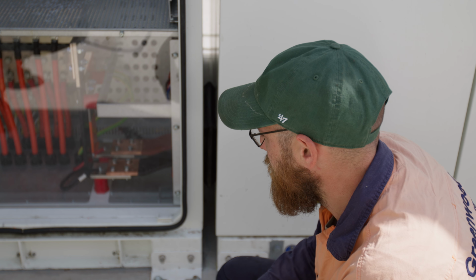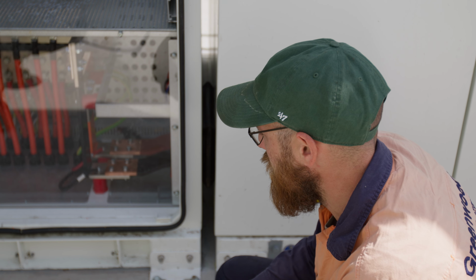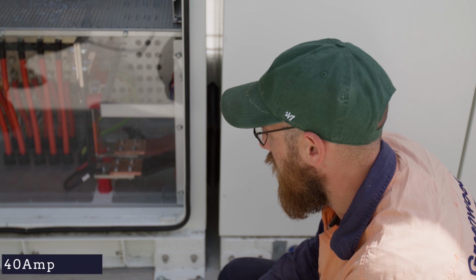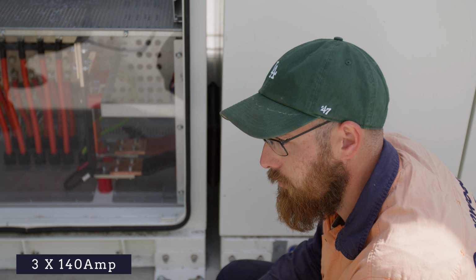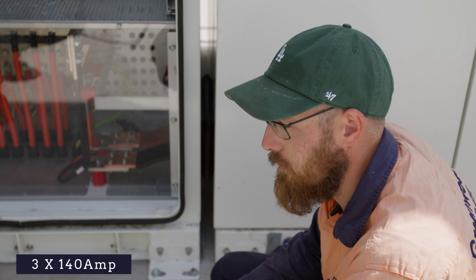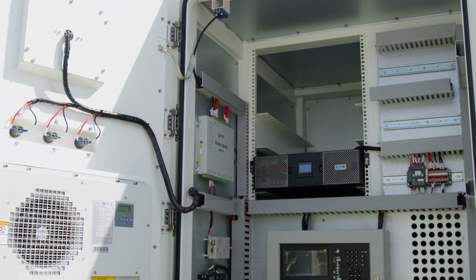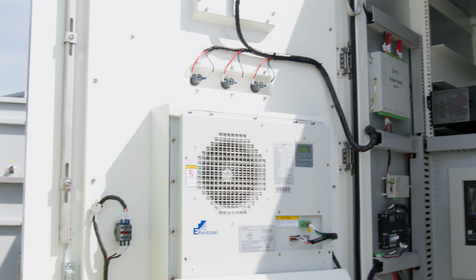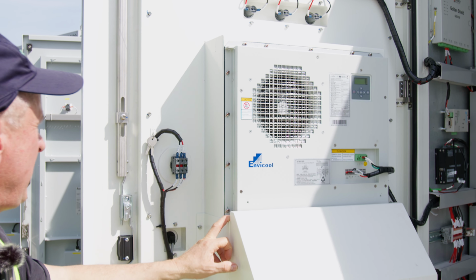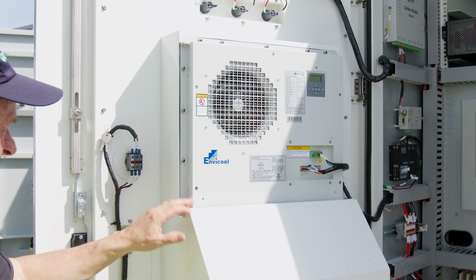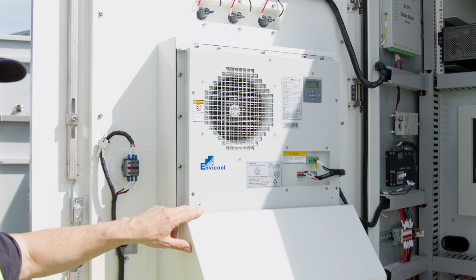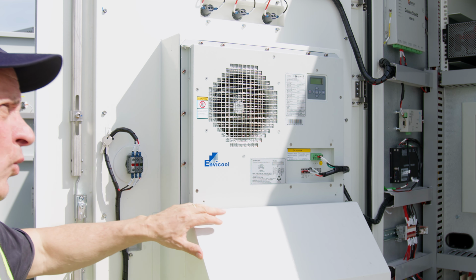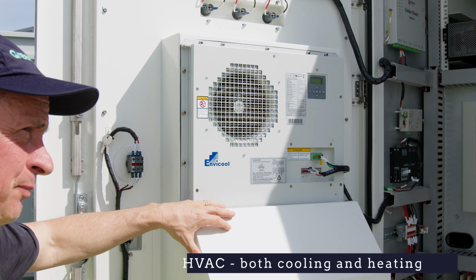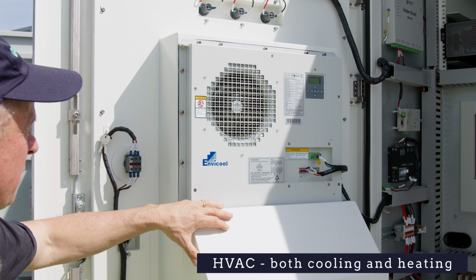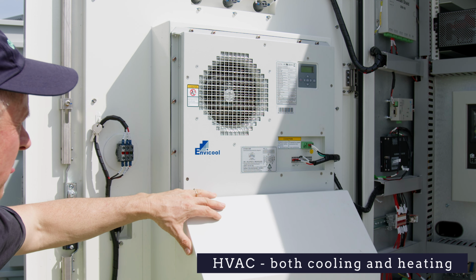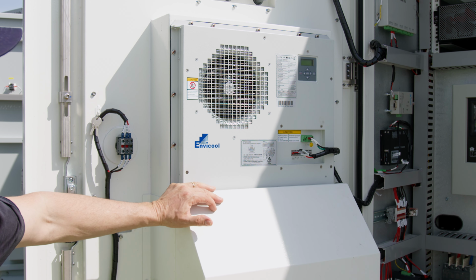Approximately. Well, each battery has the ability to charge or discharge at 140 amps, and we've got 3 of them. About 420 amps. Now, unlike the inverter cabinet with the fan-forced airflow situation, this has actually got HVAC in it. Absolutely. And it's both cooling and heating? Yes, it'll do both, so to maintain as best it can the temperature inside the cabinet at a desirable temperature.